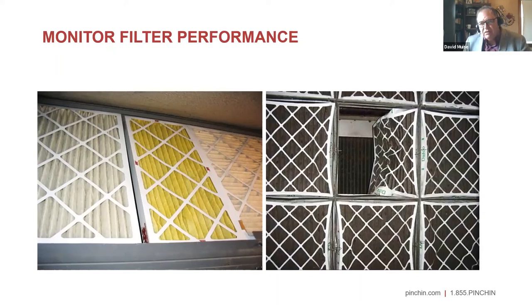The one on the right is obvious - the filter has gone through and there's a small gap on the one on the left. What's happening is unfiltered air is getting back-entrained into your supply air system. So if someone in your space has COVID, or there are other contaminants - it doesn't even have to be COVID, it could be mold or something else - it's not getting filtered out at the filtration piece. The only way to catch this is by inspecting and looking at it.